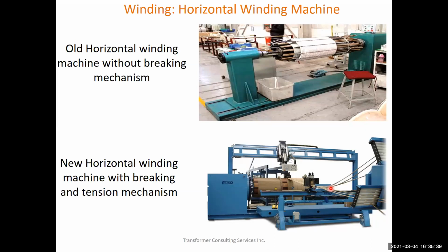So now over here, I have two pictures, one from the old shop, one from the modern shop. The top picture is from the old shop where this individual is doing the winding using hand to wind the conductor against the cylinder. Whereas at the bottom picture, you see the conductor coming from the reel is going through a braking mechanism. After the braking mechanism it is going through a socket. From the braking mechanism, the conductor all the way to the cylinder is tightened. Not only that, on top of that, you have the tensioner. Because you have the braking mechanism and the tensioner, you can wind this conductor much tighter against the cylinder.